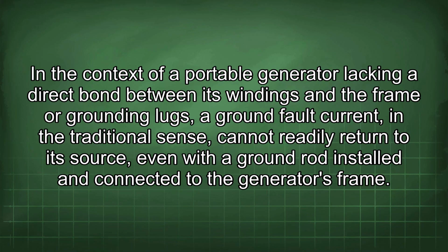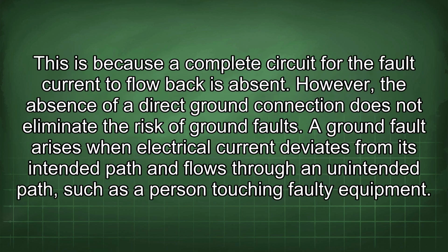In the context of a portable generator lacking a direct bond between its windings and the frame or grounding lugs, a ground fault current, in the traditional sense, cannot readily return to its source, even with a ground rod installed and connected to the generator's frame. This is because a complete circuit for the fault current to flow back is absent.